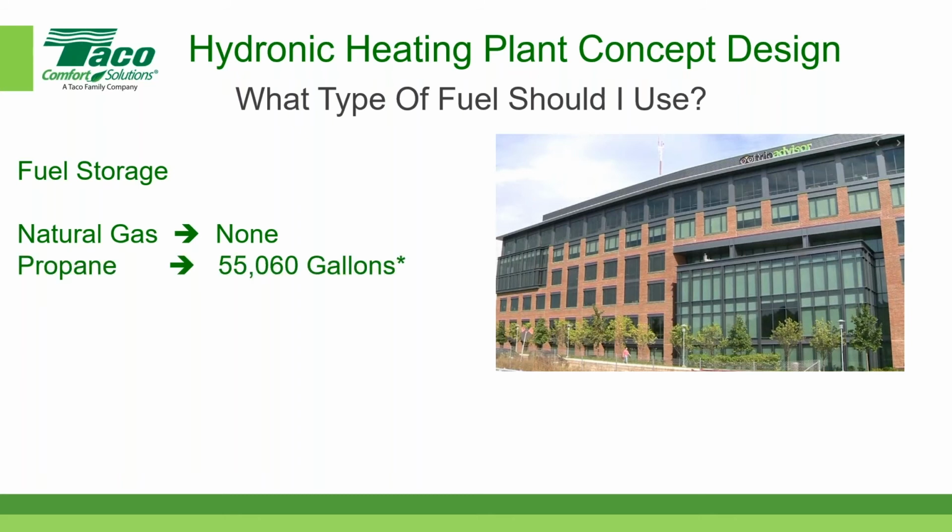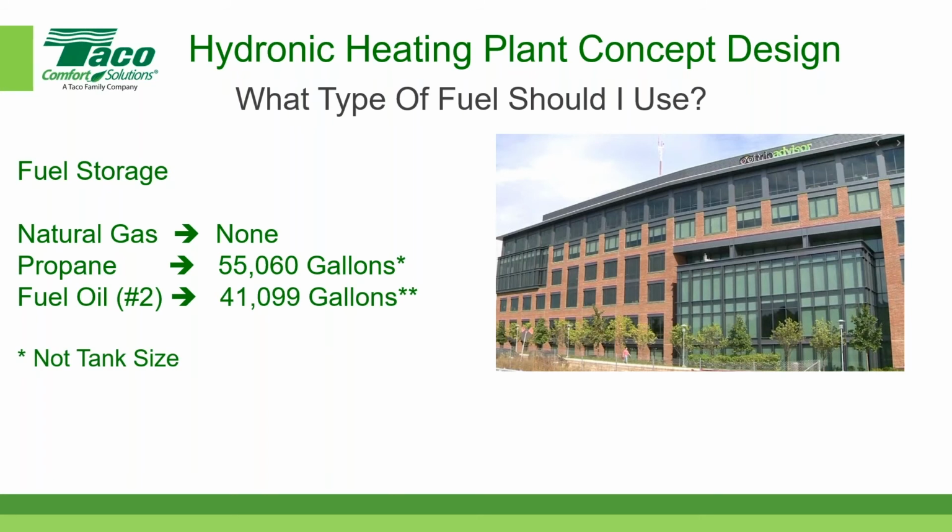However, propane does require on-site storage, and in this case, I have put in 55,060 gallons worth of storage. In a moment, you're going to see where I came up with this number. And then for fuel oil number two, I've put in 41,099 gallons. So under this first asterisk where I have propane, 55,060 gallons, that is not the tank size.